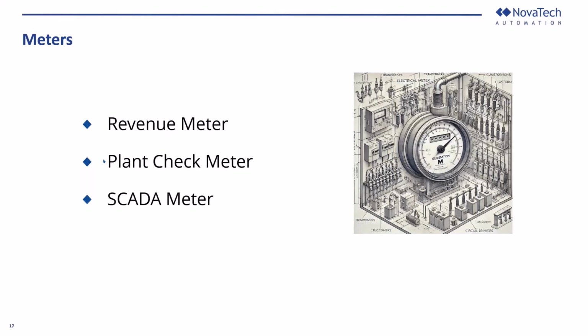The Plant Check Meter is used for verification and energy audit. It's basically for cross-checking operational performance. It serves as a backup to the main revenue meter to make sure the compliance is there and that it's as accurate as it says. So it's like a backup meter, but during internal audits you can also use the Plant Check Meter to validate what the revenue meter is giving.